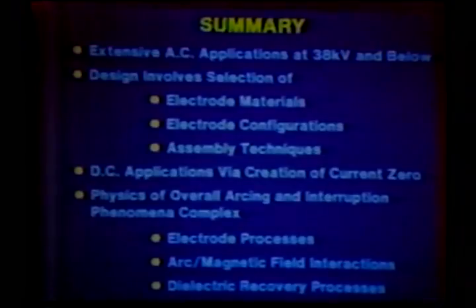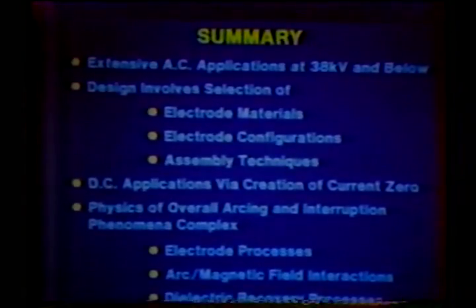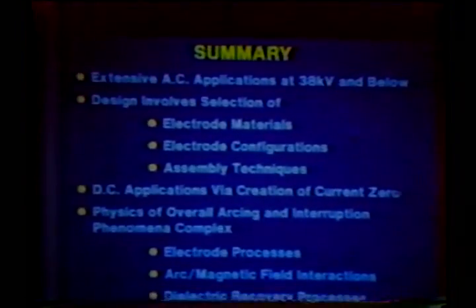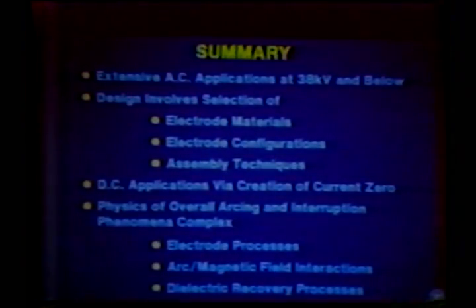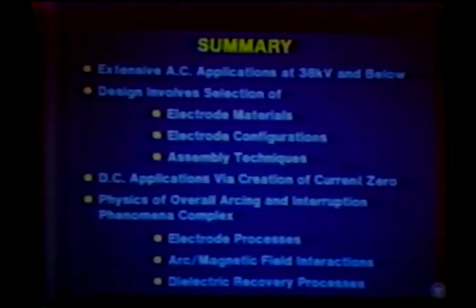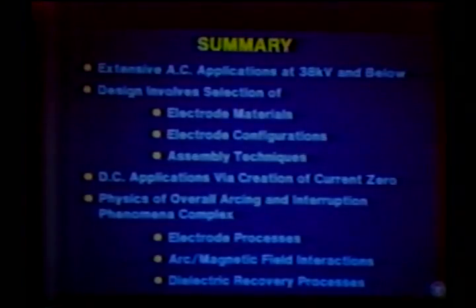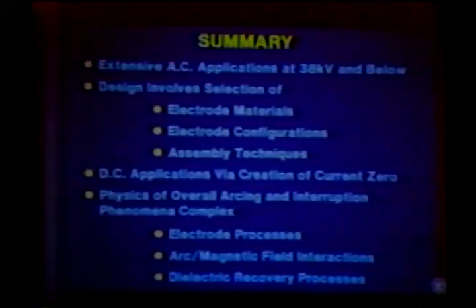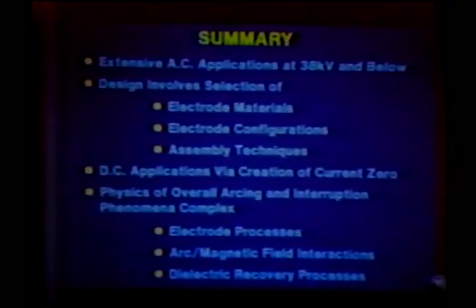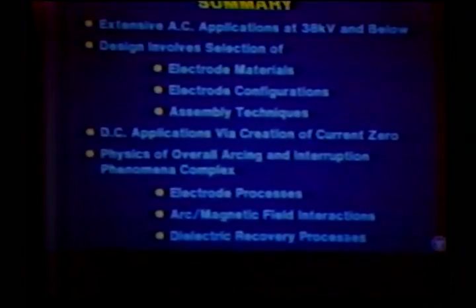In summary, for vacuum switching devices — the type of device to which much of the research heard about in the last couple of days is applicable — such devices are receiving extensive AC applications at 38 kV and below. The design involves careful selection of electrode materials, electrode configurations, and assembly and processing techniques. You can have such switching devices in AC and DC applications via the creation of a current zero. The physics of the overall arcing and interruption phenomena are quite complex, as they involve an understanding of electrode processes, magnetic field interactions, and dielectric recovery processes.